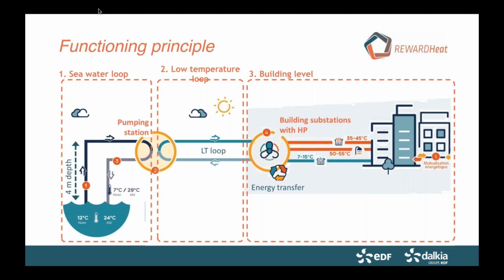Then, through the exchanger, we have the low temperature loop, or neutral temperature loop as we want to call it, because we run between 7 to 29-30 degrees. This low temperature loop uses clean water, so we have no problem with corrosion or anything, which brings the calories through the loop to the substations—the water used to extract calories for heating, or into which we inject calories during cooling. And as you see, we have no centralized production, it's decentralized production.